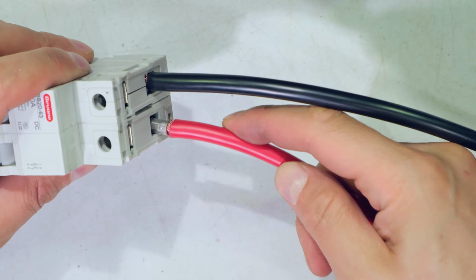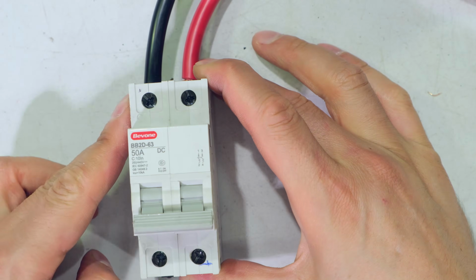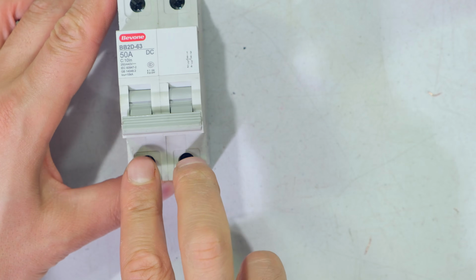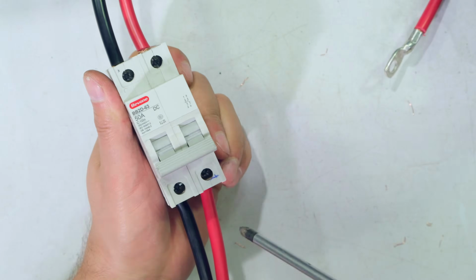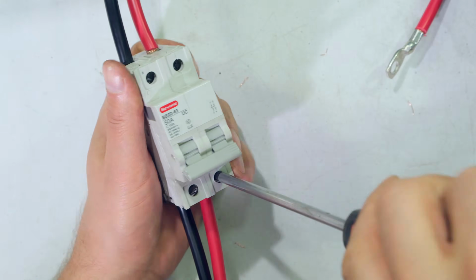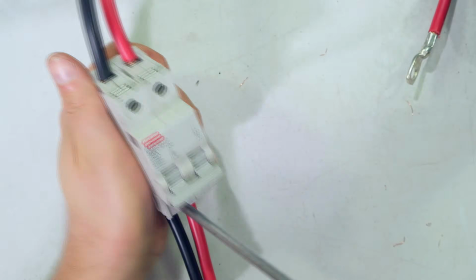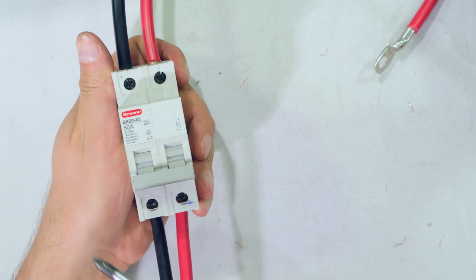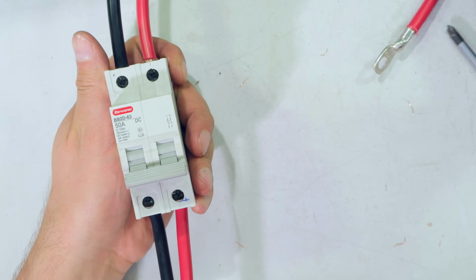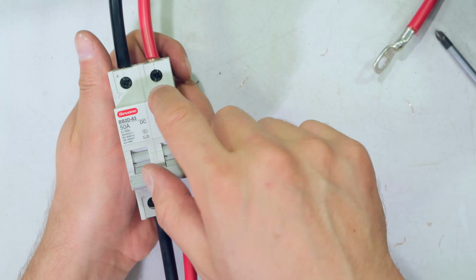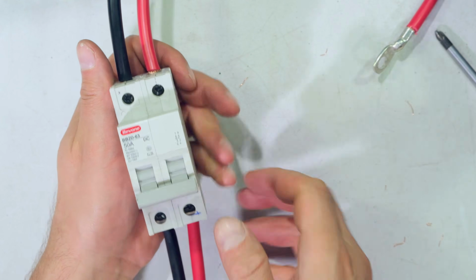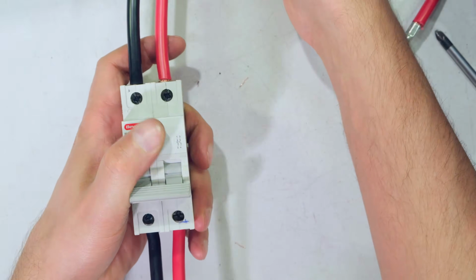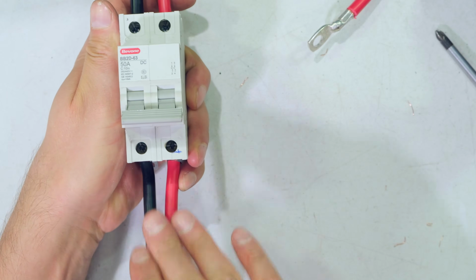Right, now I'm just inserting the positive. Right, so that's coming into the circuit breaker, and now I'm going to wire the wires going to the inverter. Right, now just do the final tightening with the screwdriver. And it's always good to go and retighten it once more, because the copper seats and it compresses, and then there's always space to tighten it just a little bit more. Right, so I have the battery coming in, and here is to the inverter.